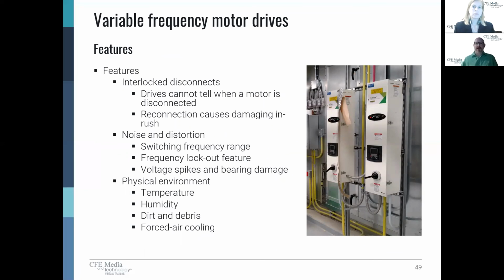If I'm going to be operating a VFD and I'm going to have that be remotely located from my motor, because say my motor's on the roof and I have to have a disconnect at the roof, I have to interlock the two. I have to interlock, meaning if that disconnect on the roof is opened, the VFD, which might be inside the building for environmental reasons, knows that that contact's been opened. And it has to know. So engineers have to specify interlock disconnects and communicate that with the mechanical engineer, or if the electrical engineer is specifying the VFD, in order to make sure that those two work together.